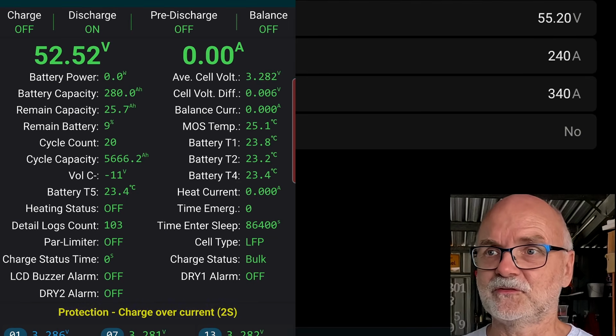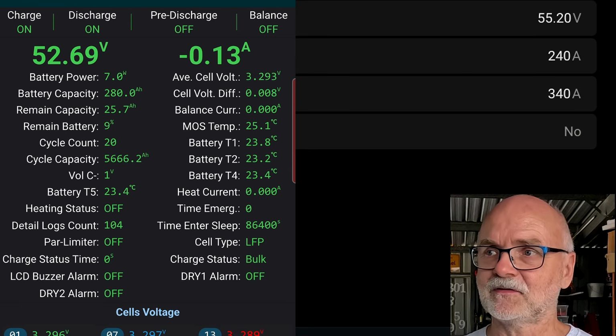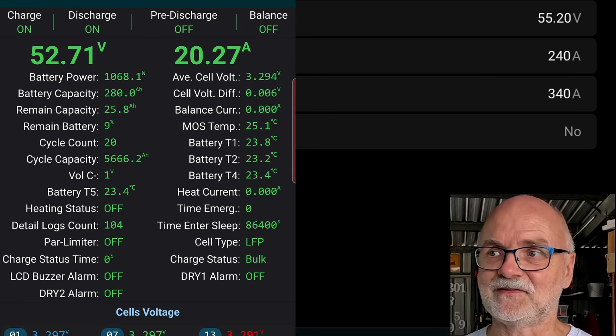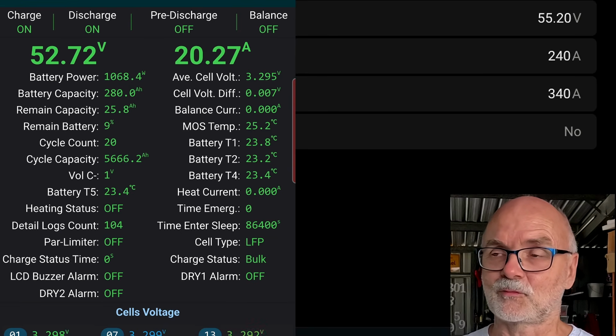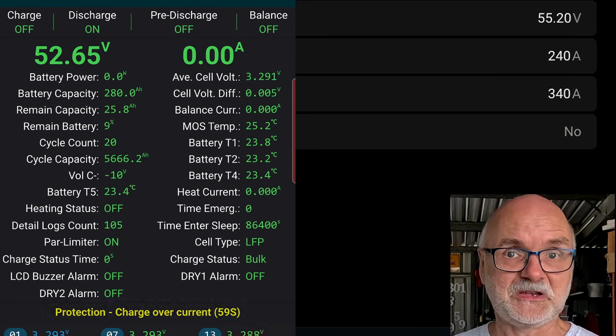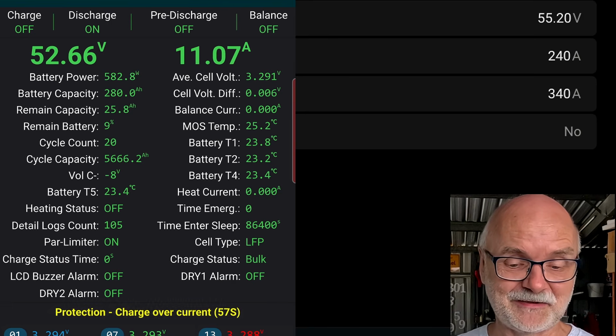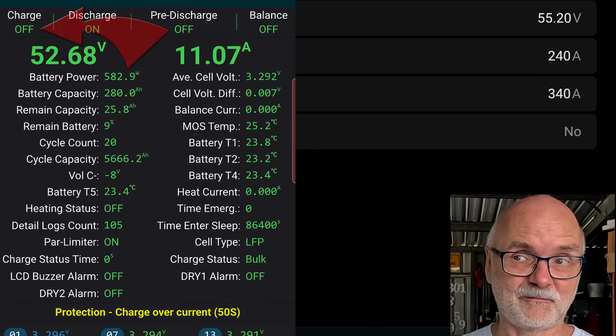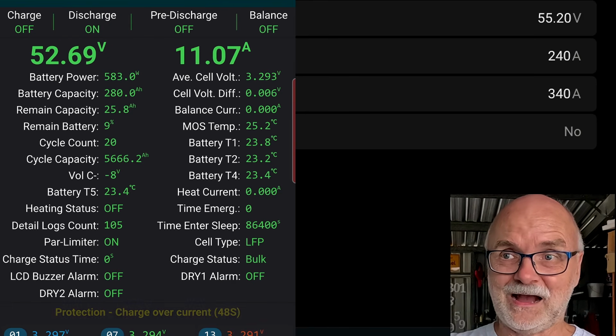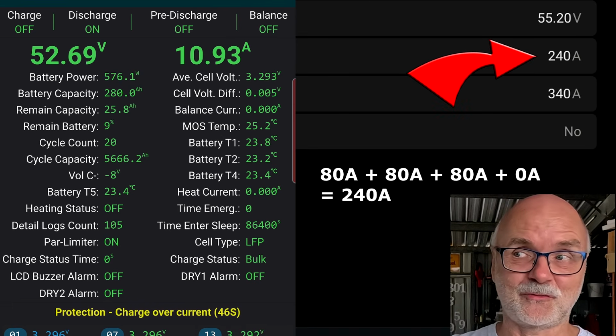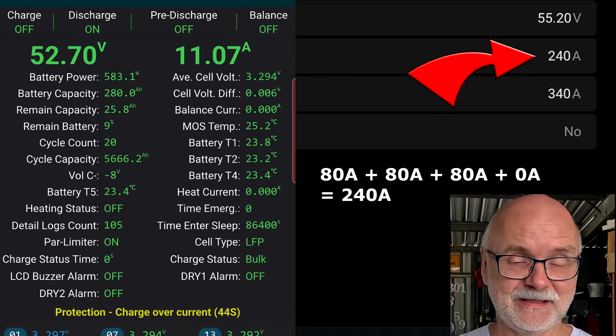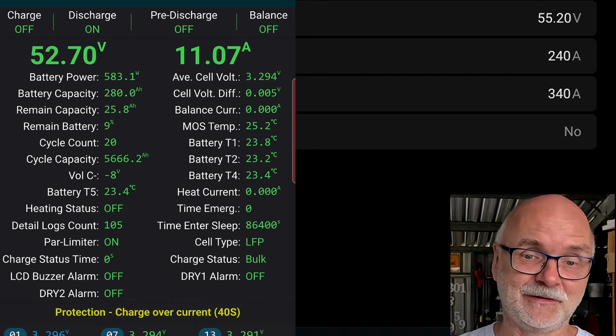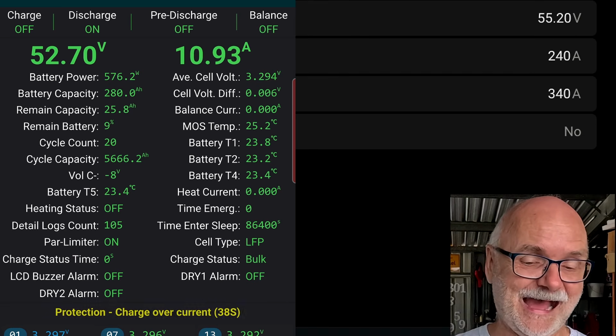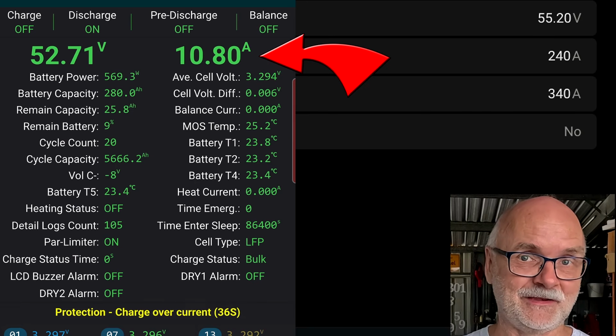We still have a reduced charge current at the moment. 1 second. Now the alarm clears. The CCL should now increase to 320 amps. No, it doesn't, because we've got another alarm, right? MOSFETs have turned off. We've got an alarm. We are charging with a reduced current of 240 amps as usual, but the parallel limiter, the current limiter, now allows 10 amps going into the battery still.